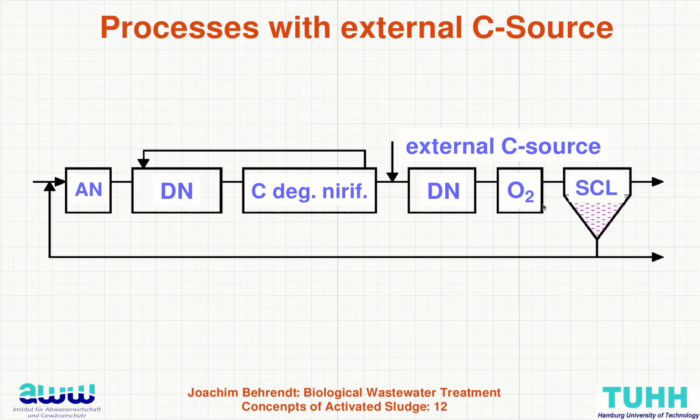In former times there was always an aeration tank afterwards. This was done for security reasons. Nowadays this is not necessary because the nitrate probes and the control systems are so good that the dosage of the C sources can be controlled very well. But finally it's nice to freshen the water with some oxygen and not bring it as oxygen-free water to a receiving water body.